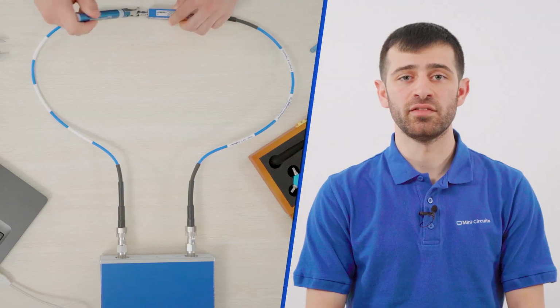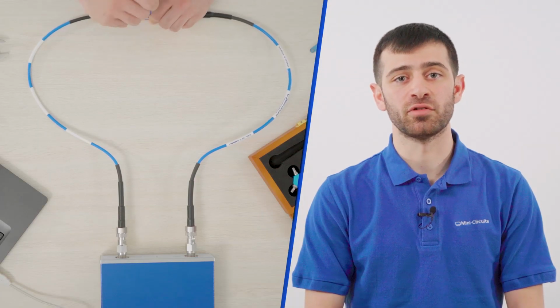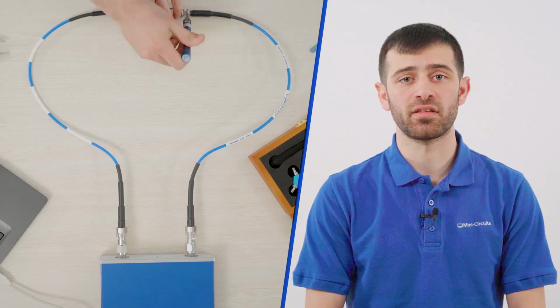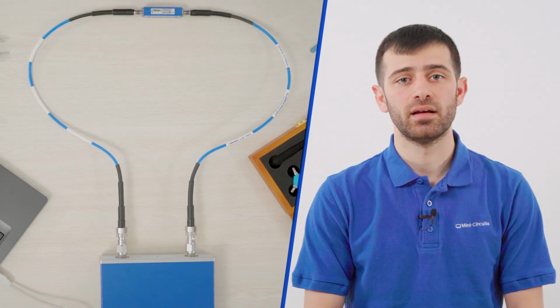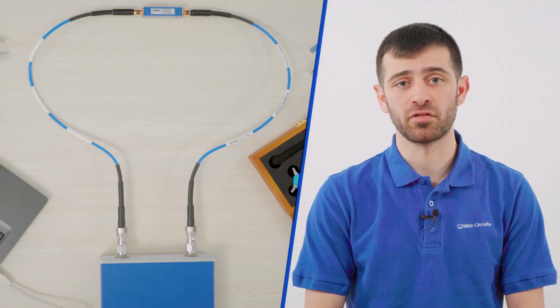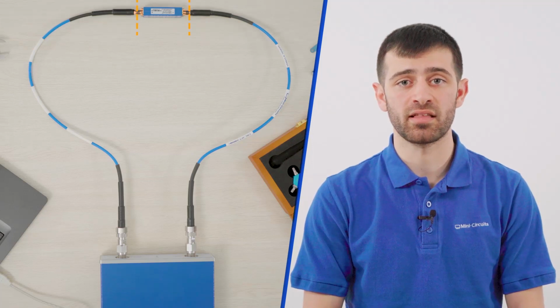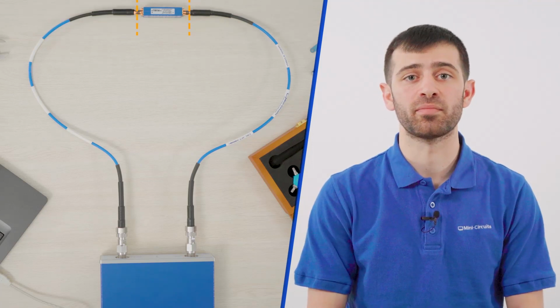Prepare the test ports of the eVNA for your specific device under test, or DUT, by using the appropriate connector savers, cables, and adapters. My DUT has two SMA female connectors, so I want to make sure that I have two male SMA connectors at the measurement reference planes.